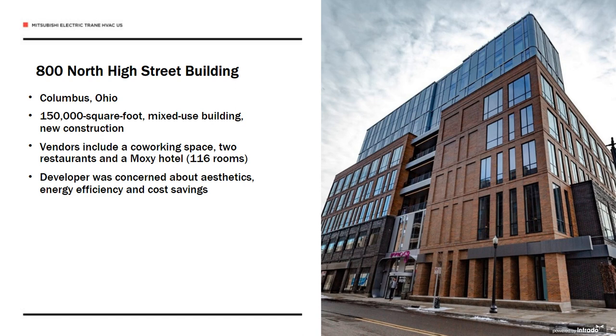The developer ultimately selected a 215-ton VRF system, along with a dedicated outdoor air system for ventilation. With VRF technology's unique ability to add indoor capacity as spaces are leased, the developer was able to defer some of the tenant improvement fit-out costs to a later date. Lastly, the developer was able to secure a rebate through their local utility based on improved equipment efficiencies over ASHRAE's baseline figures. For every kilowatt hour improved, the developer could earn up to a 10-cent credit per kilowatt hour.